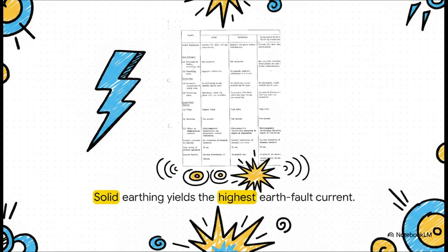And here is exactly why EHT goes with solid earthing. Solid earthing yields the absolute highest earth fault current. By letting that massive current flow completely freely, it guarantees that the protection relays are going to detect that unmistakable surge and trip instantly. We're talking clearing the fault in literal milliseconds.